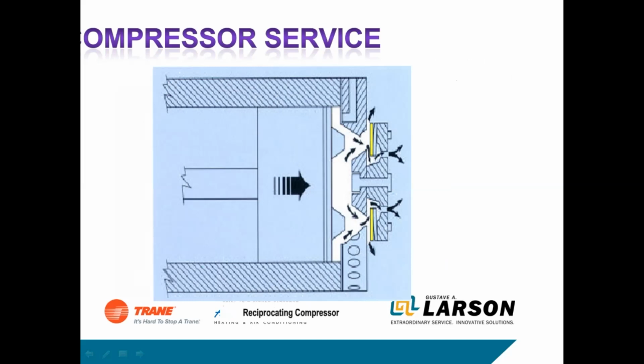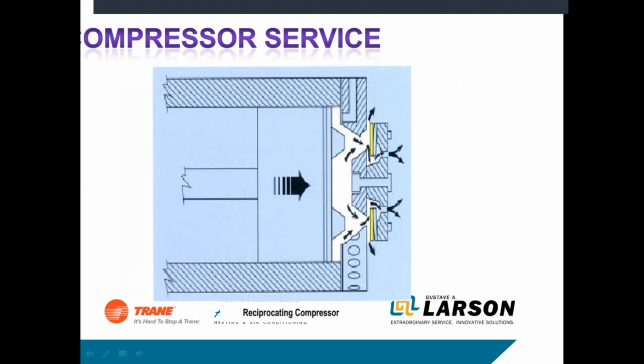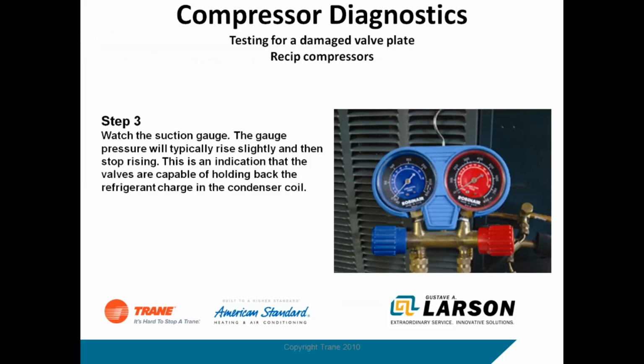Now on the old system, we had a set of reeds. Here was the valve. So every time the piston would come up, it would discharge through the valve. And then when the piston would go back down, the valve would close and it would draw the refrigerant back in through the ports. You know, pretty simple operation. You know, they don't like liquid. If you start putting liquid into a piston, it takes those valves out pretty quick.